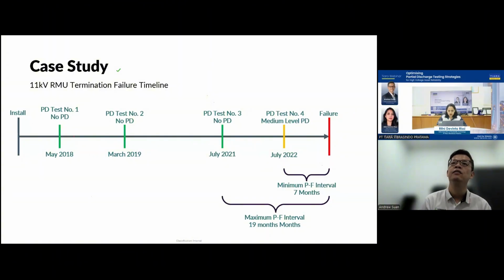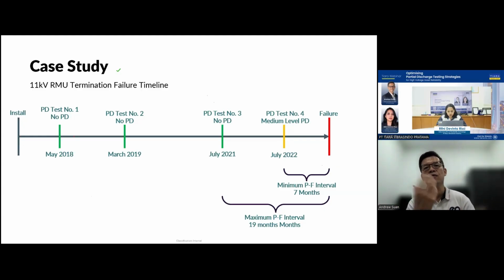And then, maybe during the yearly shutdown, the airport engineers would be able to save the RMU, detect the problem, and then try to fix it, and then put back the failed cable termination - do a proper cable termination - and save the switchgear from having a flashover. So that is the maximum. So from 19 months, because I do it yearly, it shortens the point to failure interval to 7 months.